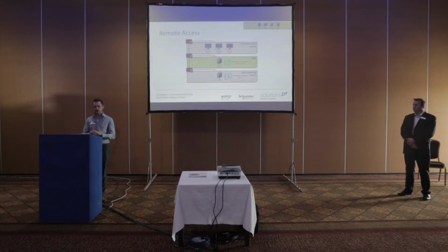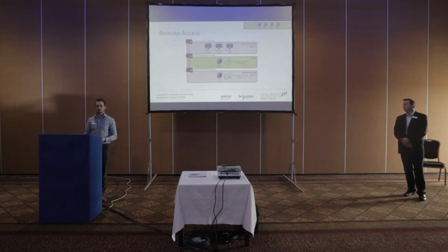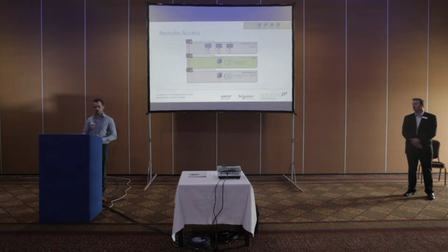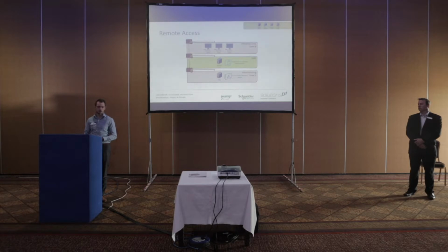But it's when we want to get it out to that enterprise layer or even out to a wide area network. And built into the In-Touch Access Anywhere scenario, and this is a software perspective, they have something called an In-Touch Access Anywhere secure gateway. So we install it at the demilitarized zone layer, and it's very, very similar to what you'll see with things like your VPNs on your network. So when you're logging in and you want to be part of that network when you're external, it's a very similar process. So it opens up the right ports in the right directions, but it'll only ever allow you access to that server at that bottom manufacturing layer.